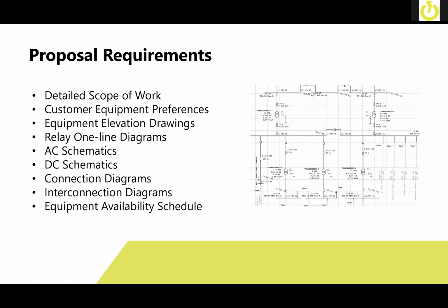A lot of times, unfortunately, they may have some older electromechanical relays that are rather small, and these panels do get crowded sometimes. So whenever we're trying to put multiple relays in a single panel, along with multiple test switches, multiple new control switches, and proper spacing in between to be able to mount everything and wire it all out correctly, it can take up more space than the old installation used to.